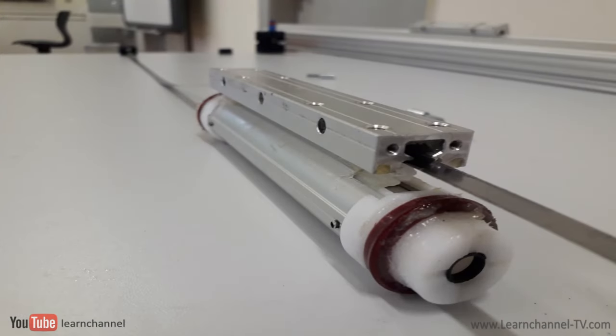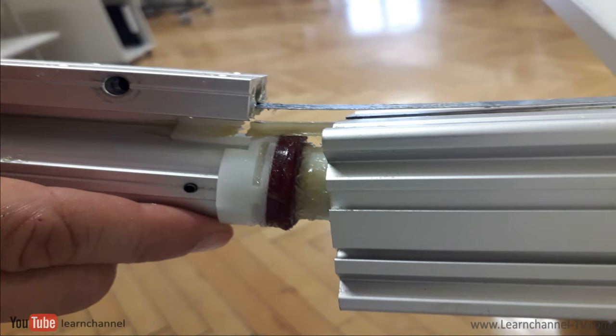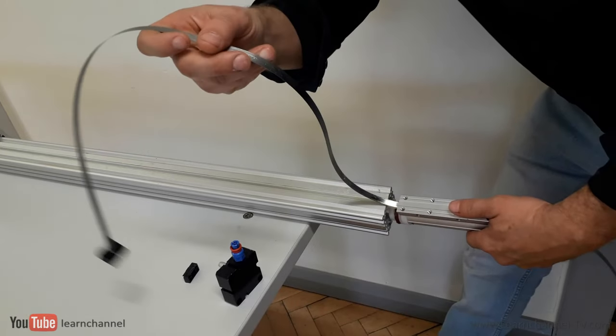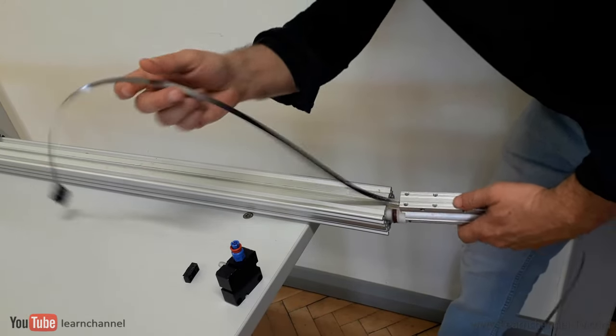Inner and outer bands may wear over time as they stretch. As a result, you can get air leaks and loss of air pressure. It is up to the maintenance to replace these bands, especially for expensive cylinders.